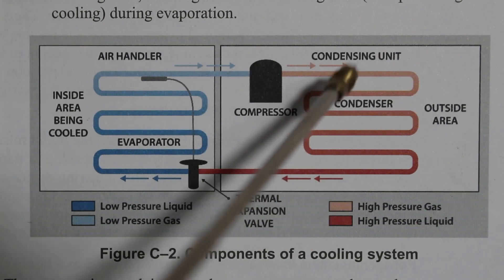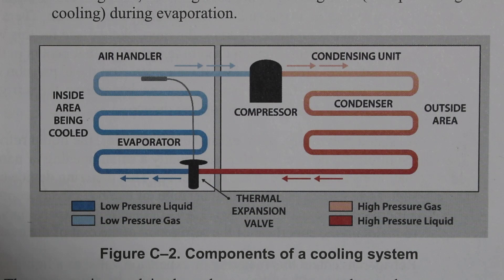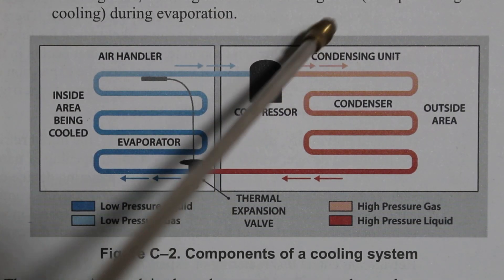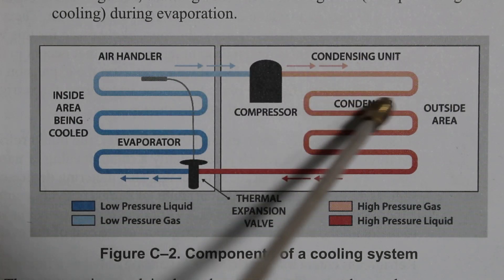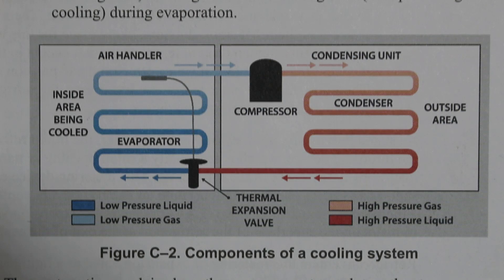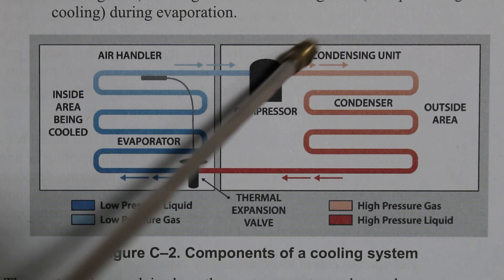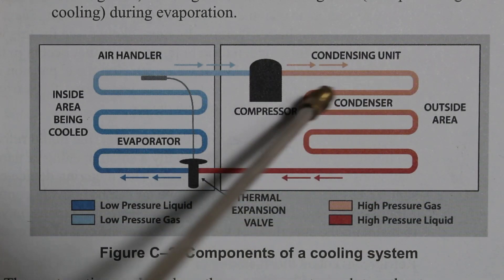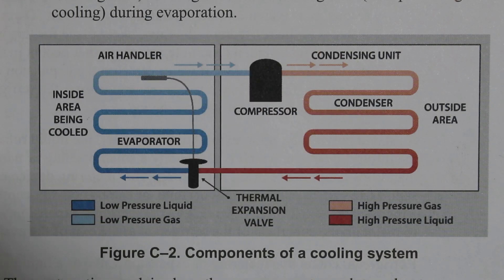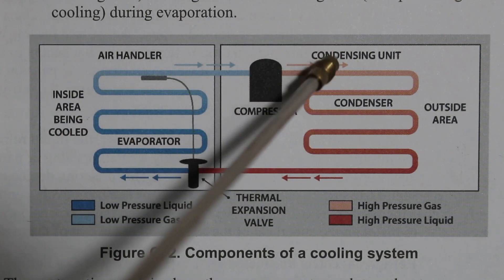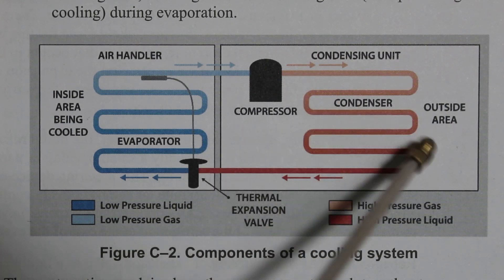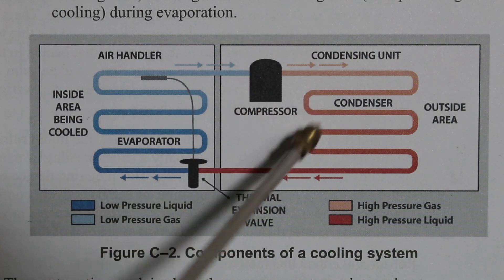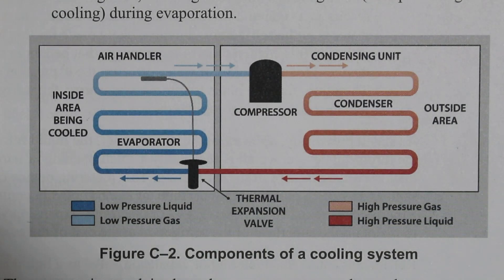We are entering our condenser as a high pressure gas — specifically a high temperature, high pressure, superheated vapor. At about the midpoint of our coil our refrigerant is saturated. At this point we have what is known as latent heat of condensation — latent heat being the change of state but not the change of temperature. We enter as a high pressure gas and leave as a high pressure liquid; specifically, we change state from a high temperature, high pressure, superheated vapor into a high temperature, high pressure, sub-cooled liquid. To learn more about superheat and sub-cooling, I will link a video in the description.